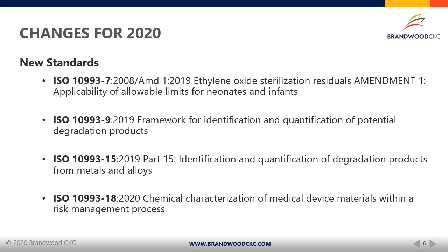So Part 7 was amended. The amendment is specifically to allow application of this standard to the allowable limits for neonates and infants. This is essentially a how-to when it comes to derating the allowable limits of ethylene oxide on a device after sterilization for a low body weight application. Clearly, when you have a low body weight, then the amount of ethylene oxide that can be tolerated goes with that body weight, and so it has to be derated. And the standard is quite instructive in its amendment to show how that should be done.